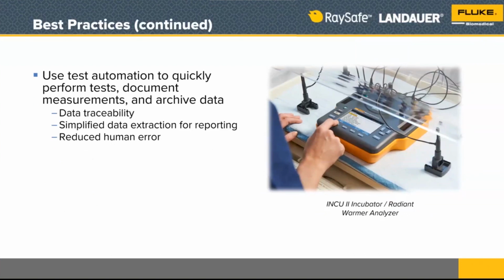We can automate some of these tests, and we in fact do in the INCU2 incubator analyzer, so that if you want to run the full standards test right from the standard, you can do that. But there are also a couple of other ways to run those tests. You can select some, but not all, of the tests required under the standard, or you can simply connect all the sensors and run a test based on whatever you connect. So I usually connect all of the sensors, put everything inside the infant incubator, and then begin running my tests, run it for about an hour so that we cover that STC requirement. And then after that, I also run electrical safety, which is about another 10 minutes.